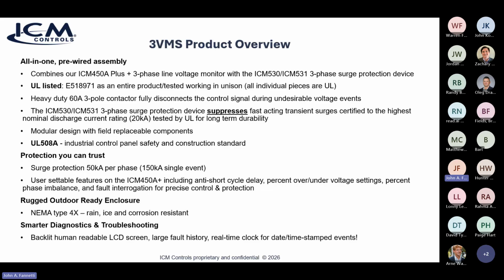So you have it all in one package with a nice contactor built in. It's a UL listed device. It's got a heavy duty 60 amp 3-pole contactor, which fully disconnects the load. You've also got one of the best surge suppressors on the market, the 530, 531, with a high nominal discharge rating of 20 kA, which means it can take a lot of hits before it goes out. And remember what the surge suppressor does: it absorbs and dissipates the surge. That in itself doesn't disconnect you from the line. Voltage issues like phase loss, phase reversal, phase unbalance, over and under voltage will disconnect you from the service line. But surges are absorbed and dissipated by the TMOVs.